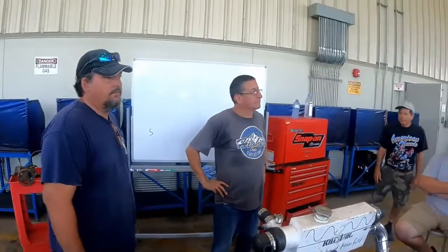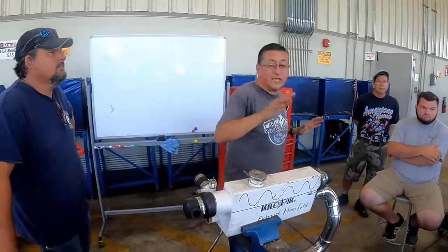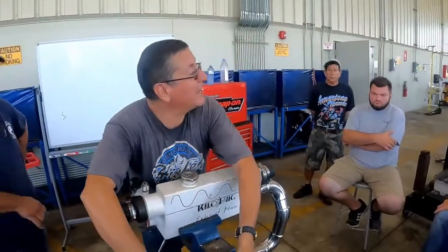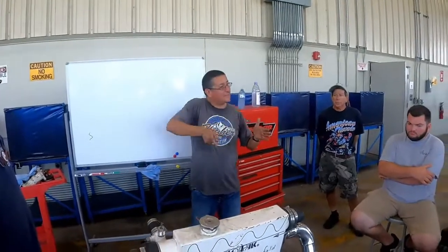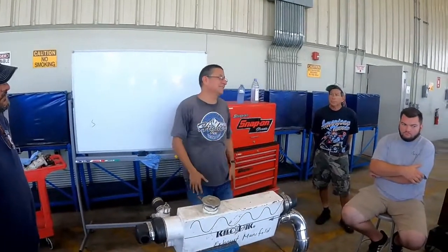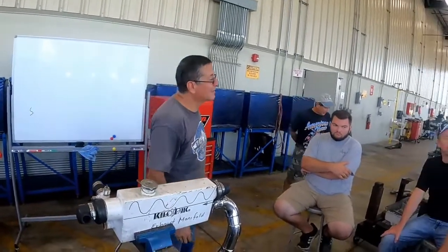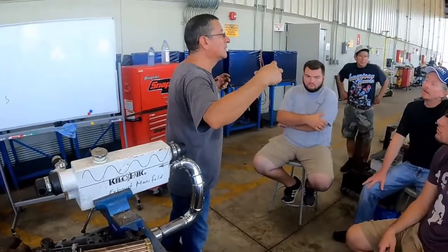What about that engine over there, the CATs, and different heat exchangers, that one with the aluminum plates? It's the same, but instead of pipes, you have 26 or 36 plates with rubber in between each one. You put them together and you create that pack. It's exactly the same, with plates. So on that engine, if you sent out that sample, you'd get high aluminum because that's aluminum?